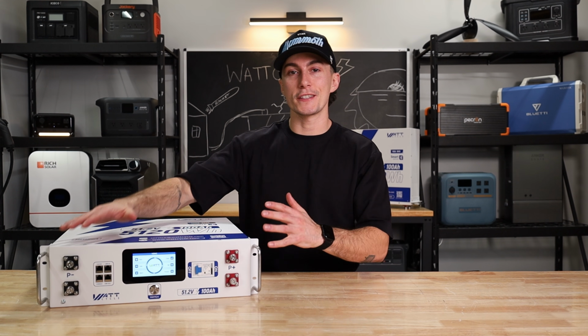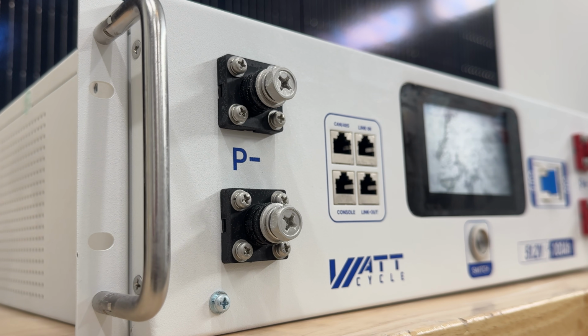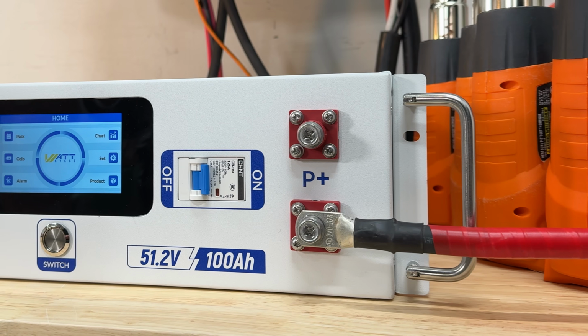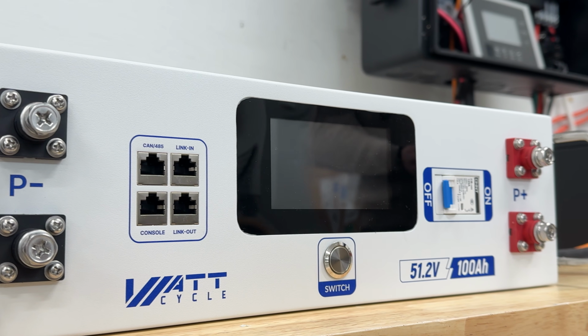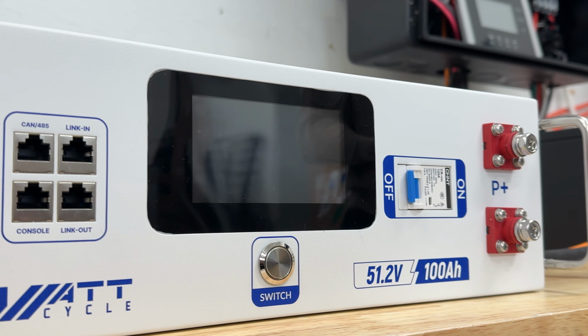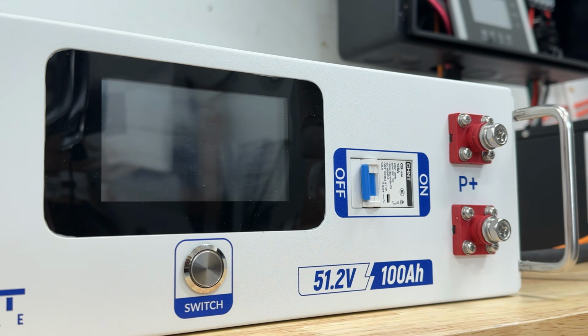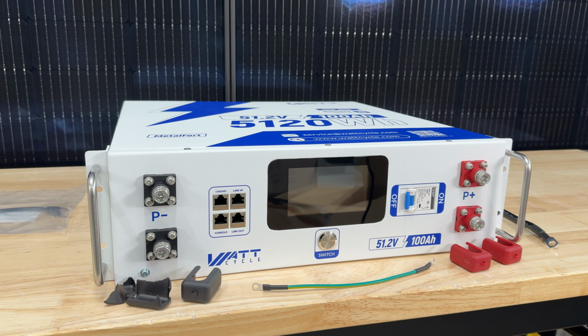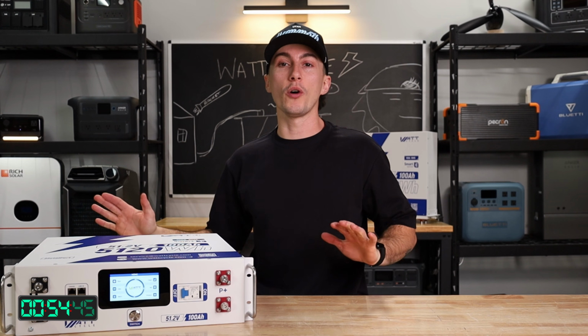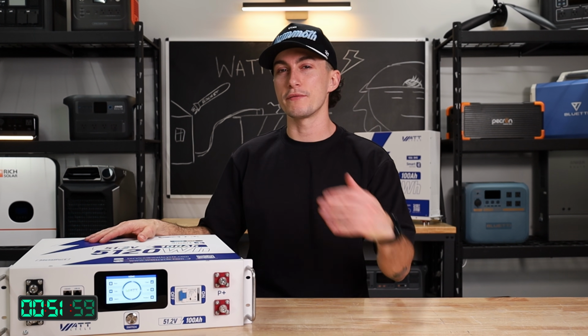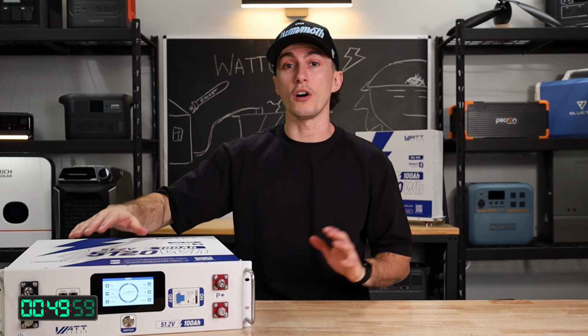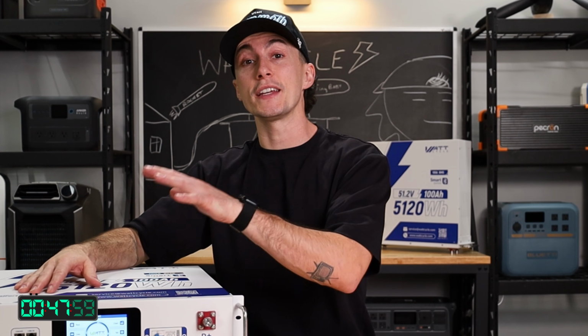In terms of connections, you have your 2 negative terminals on this side, 2 positive terminals right here. You have your breaker on the front, and your screen/BMS switch right there. And you have your stack of communication ports on the side. Otherwise, there's no other ports on this battery. It's very simple—all the dip switches, protocol, and identification are built into it.